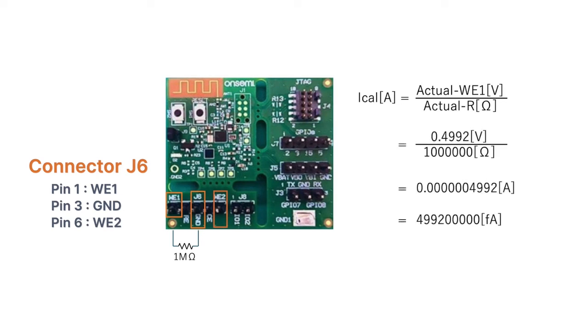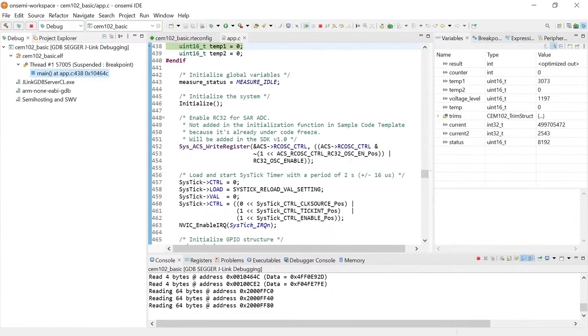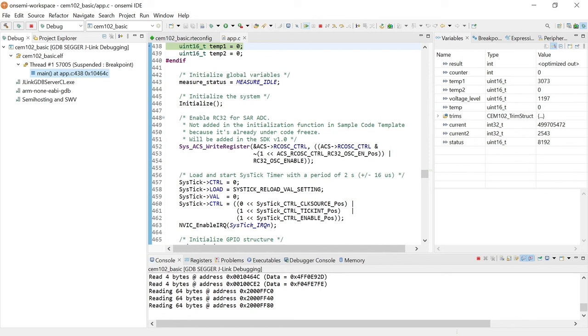As a result, the theoretical current value at WE1, I_cal, can be determined by this equation. Now, if you navigate back to the TerraTerm application, it shows approximately 499.5 nanoampere. This unit is measured in femtoampere. As you can see, the CEM-102 is highly precise and it can measure impedance of sensor or current in this way. You can also take other various measurements by changing the firmware.